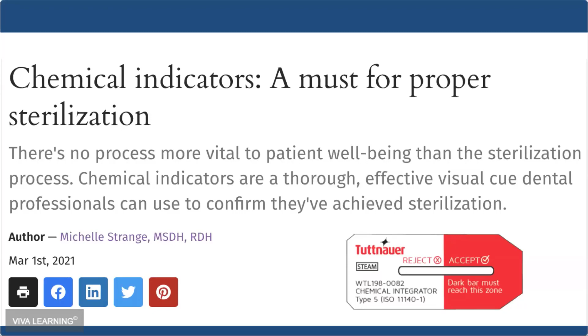And just so you know, there are 6 types of chemical indicators. So you want to know which ones you use and which are recommended for your equipment. You can find more info probably with your equipment's instructions for use, and also with your instruments' instructions for use. I know I mentioned this already, but I prefer a type 5 integrator in every single load in combination with a type 4 indicator. If you're wrapping your cassettes, remember a type 4 needs to go inside of the cassette. And if you're feeling really spunky and crazy, I love the idea of putting that type 5 inside your cassettes, especially surgical cassettes, because that type 5 is going to tell you it's met all the critical variables: your time, temperature, and pressure.